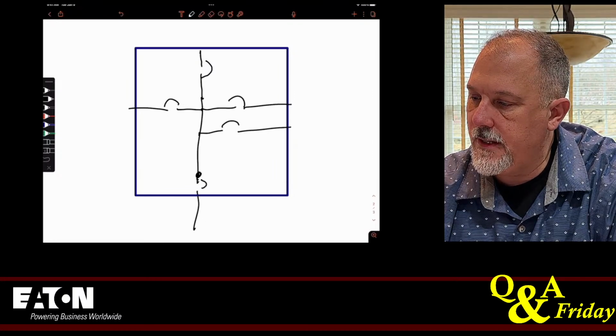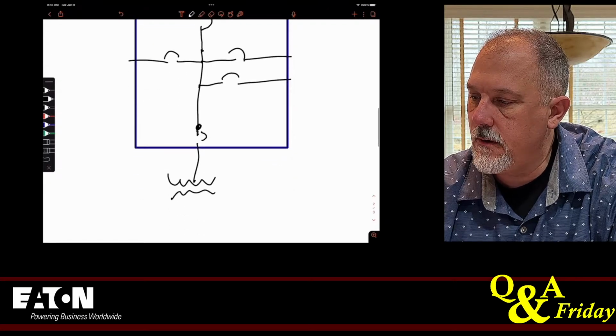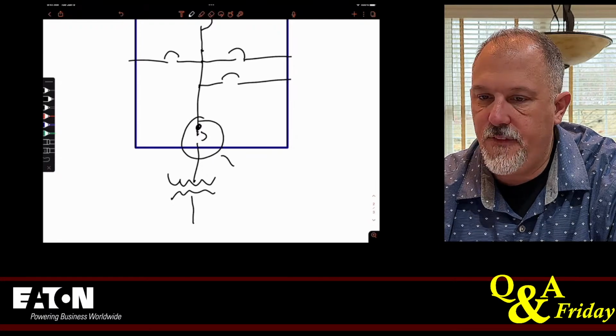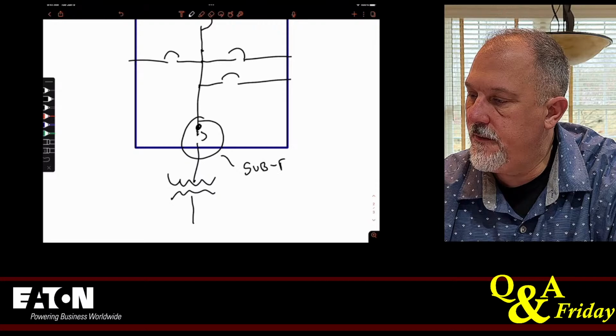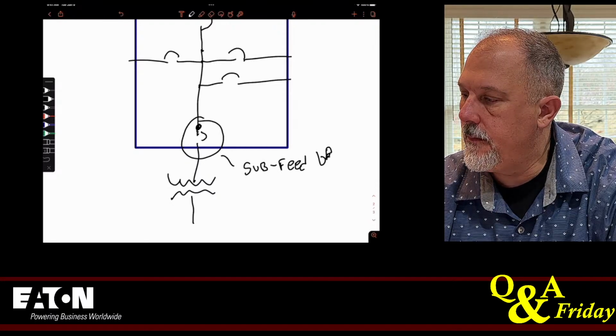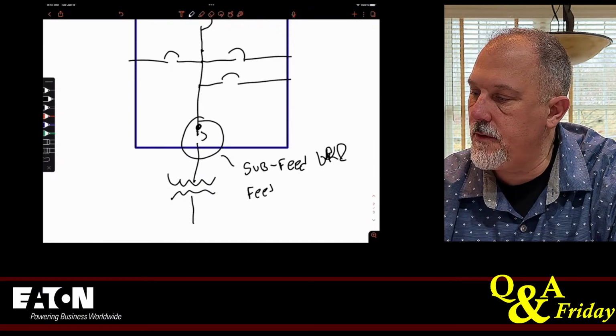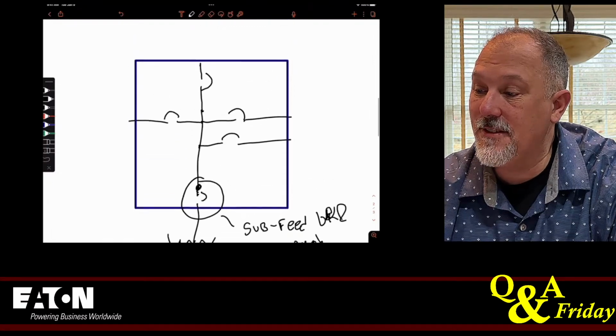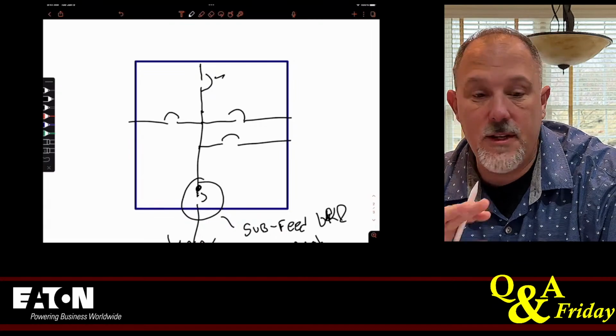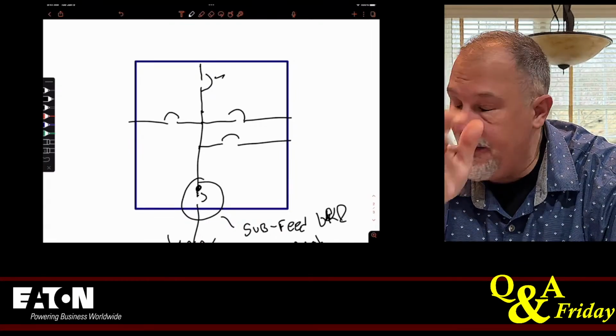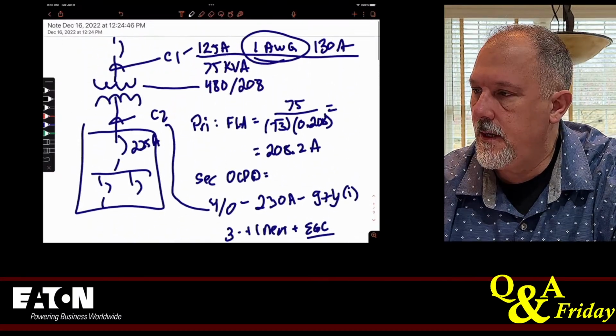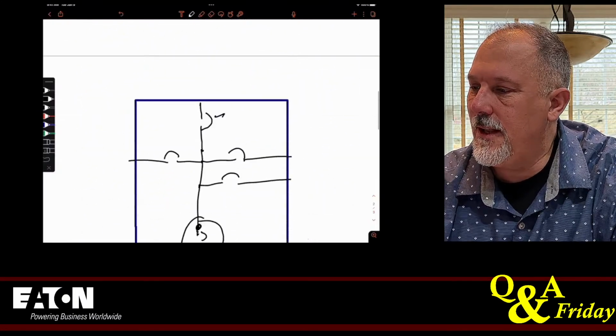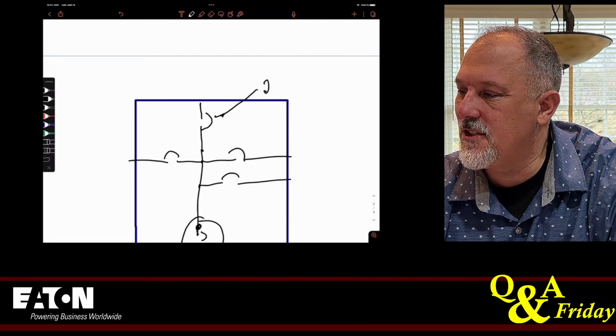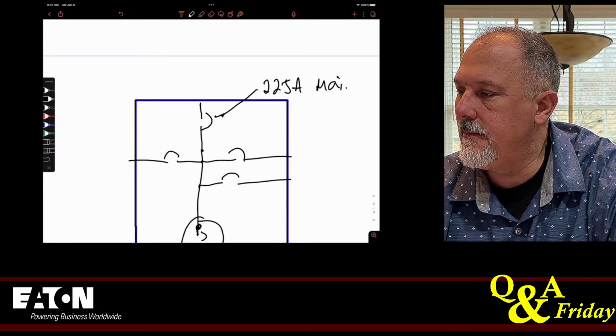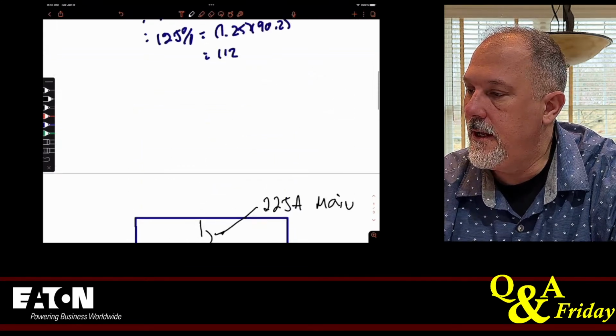We could put a breaker down here feeding our transformer. This is a feed through. Sub feed breaker. I sometimes refer to those as feed through. And here's the other funny part. The primary, we said 130 amps, right? So let's say this is a 225 amp main. That was the maximum size, 225 amps.